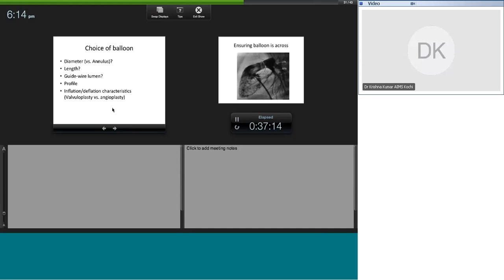However, the exception is in dysplastic valves that don't yield. Then you can oversize a little bit and try to get past it. But by and large, if you have a 6 mm balloon, you can pretty much get by with 6 or 7 balloon. 6 mm annulus, you can get by with 6 or 7. You don't have to go to 8 or 9. That is incorrect. It's really not needed. So it's important to recognize that you don't oversize it as much today as you used to do in earlier days.